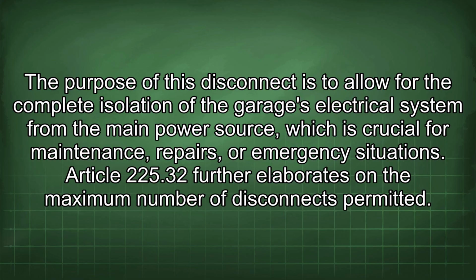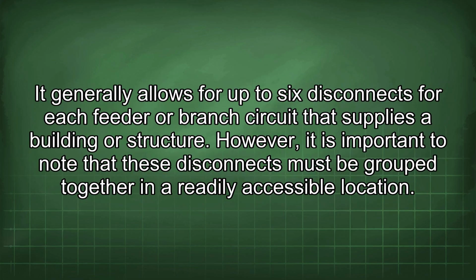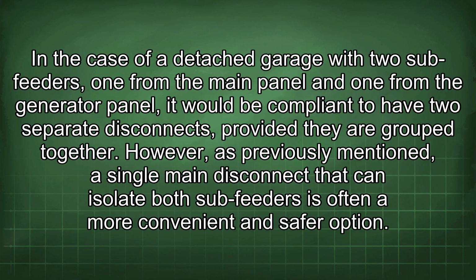Article 225.32 further elaborates on the maximum number of disconnects permitted. It generally allows for up to 6 disconnects for each feeder or branch circuit that supplies a building or structure. However, it is important to note that these disconnects must be grouped together in a readily accessible location. In the case of a detached garage with 2 sub-feeders, one from the main panel and one from the generator panel, it would be compliant to have 2 separate disconnects provided they are grouped together. However, as previously mentioned, a single main disconnect that can isolate both sub-feeders is often a more convenient and safer option.